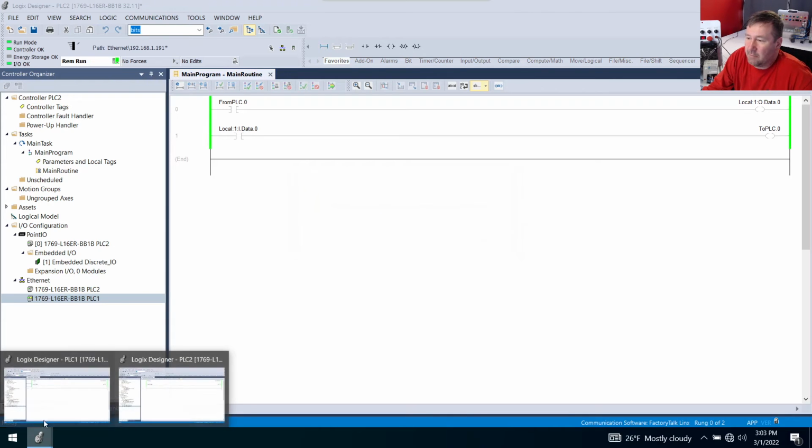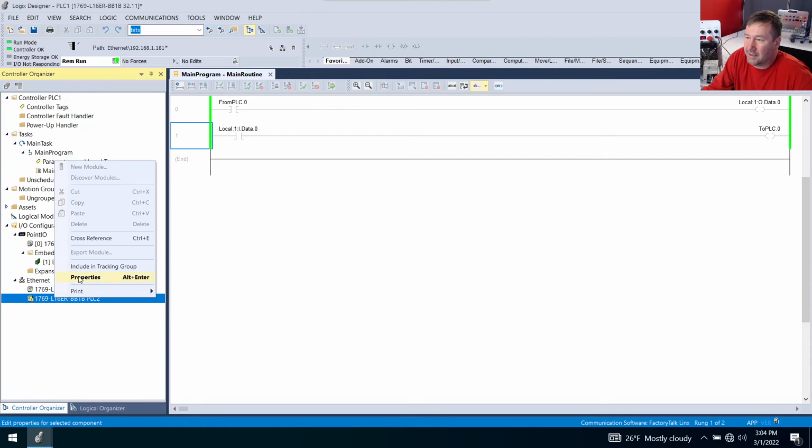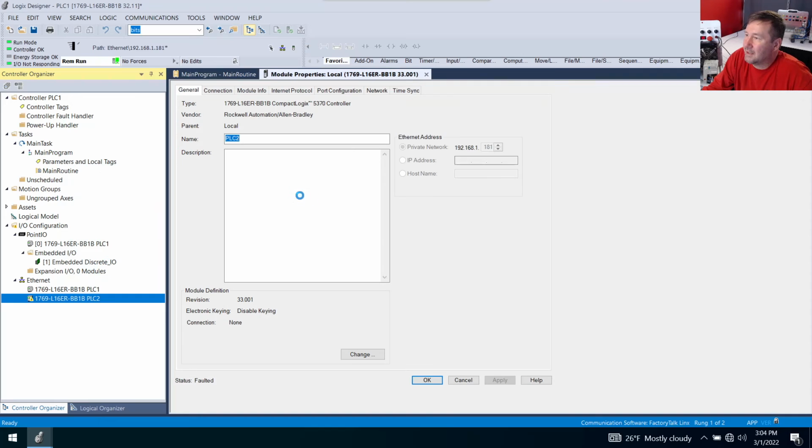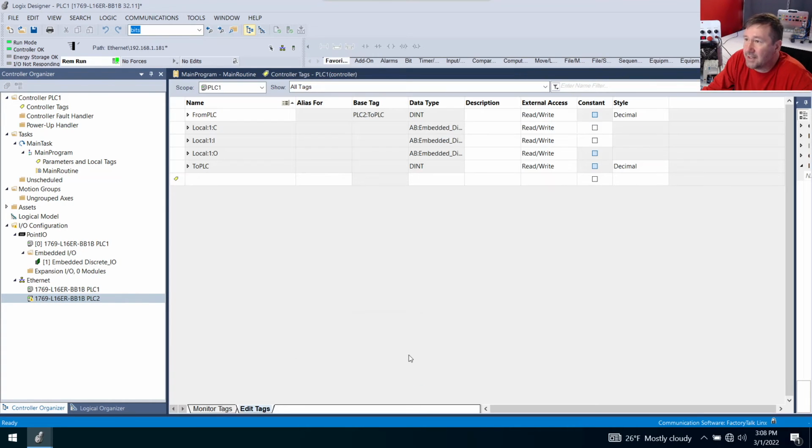Now let's go to PLC 1 and double check it. Well, apparently we have another learning opportunity because its I/O is not responding also. So let's right click it and go to Properties and Connection. Connection request error, cannot consume tag ToPLC. Now here's what I did, and honestly I don't know where I did it wrong, but this PLC, PLC 1, is 192.168.1.181, and I have PLC 2 as this.